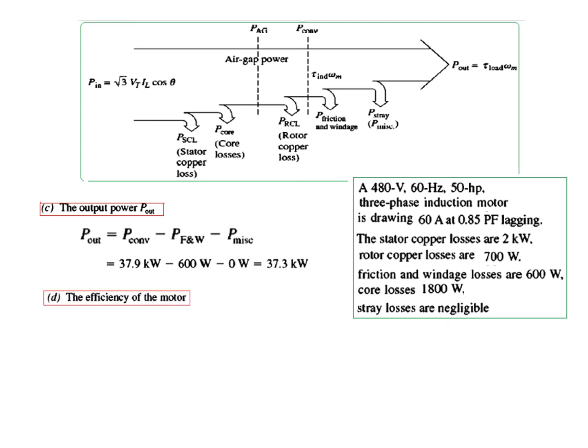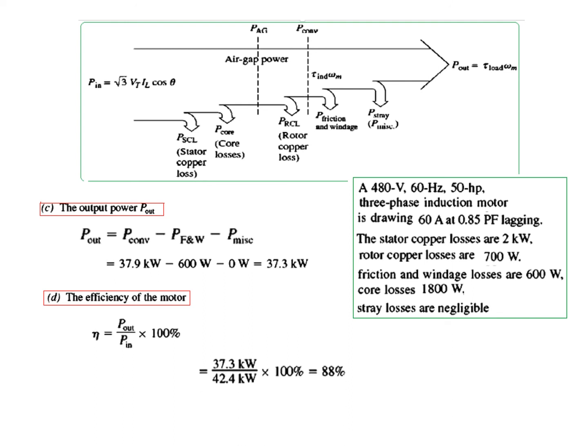Finally, the efficiency of the motor is output divided by input times 100%. Output is 37.3 kW and input is 42.4 kW, so the efficiency is 88%. I hope this gives you an understanding of how to solve this problem by following these steps. Thank you.